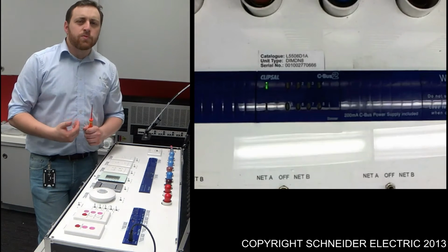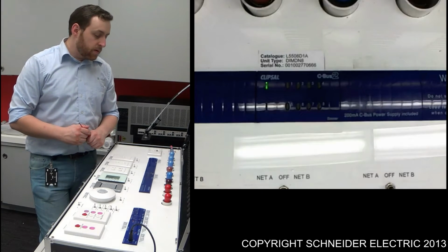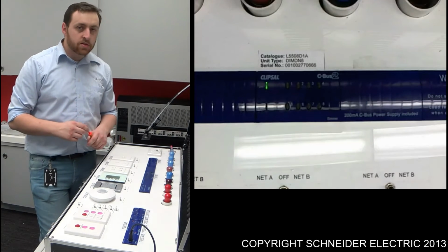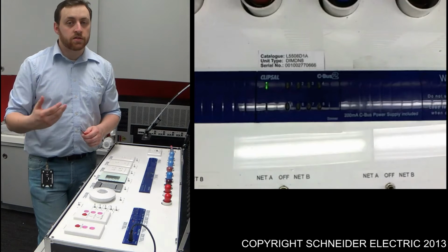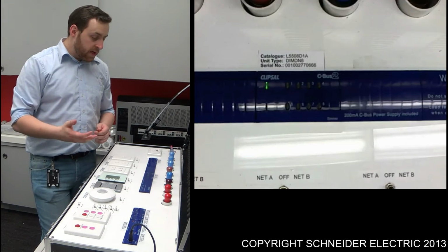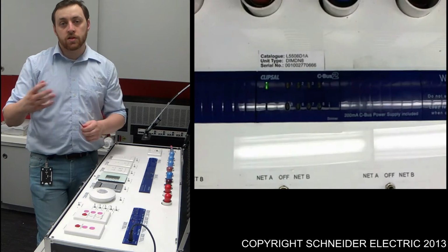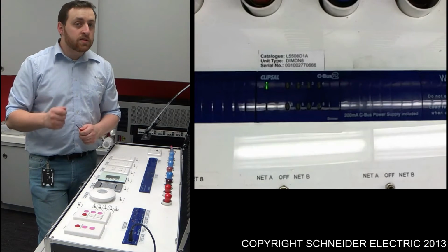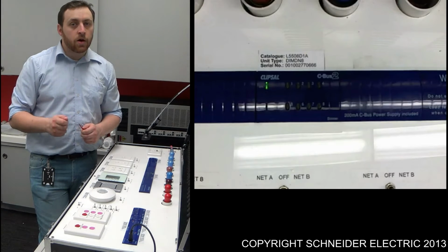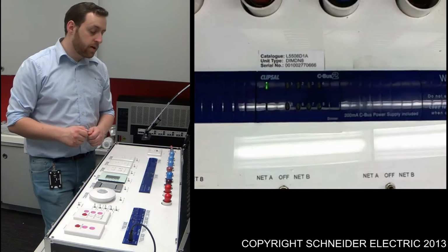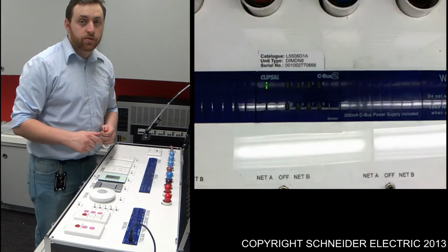The other reason, this is probably the most common reason, is basically the CBus network has lost its CBus clock. Now what that basically means is that none of the units are able to get in sync with each other to basically communicate. There is a really easy way of getting that back, and I'll quickly just show you now. And what it is, basically, is entering Learn Mode.